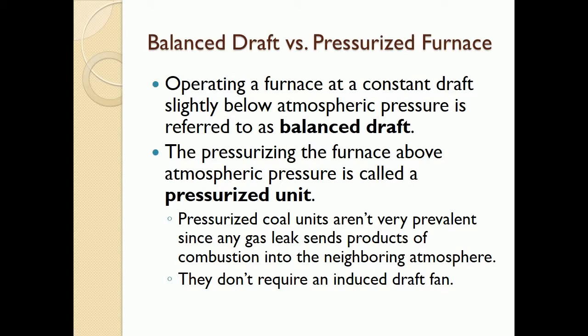Balanced draft versus pressurized furnace. Operating a furnace at a constant draft slightly below atmospheric pressure is referred to as balanced draft. Pressurizing the furnace above atmospheric pressure is called a pressurized unit. Pressurized coal units aren't very prevalent, since any gas leak sends products of combustion into the neighboring atmosphere. They don't require an induced draft fan.